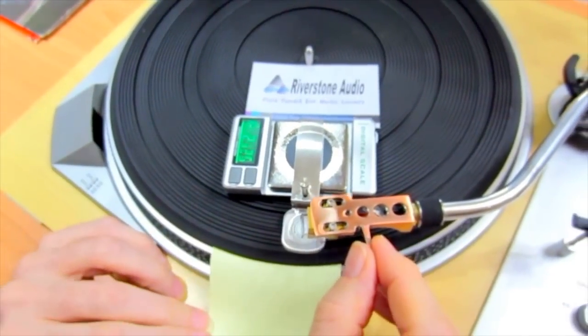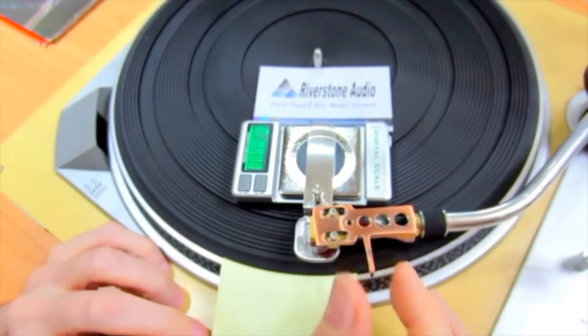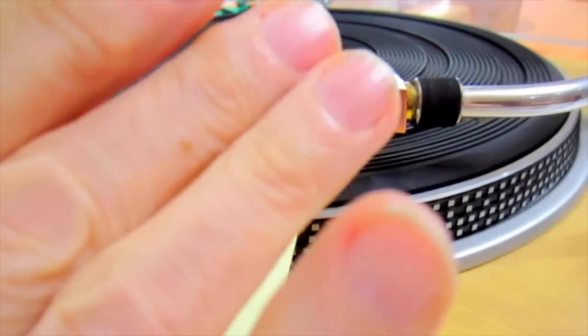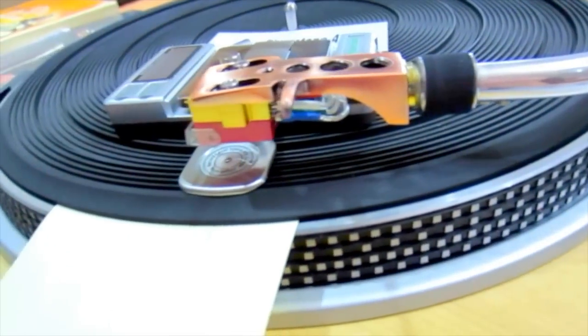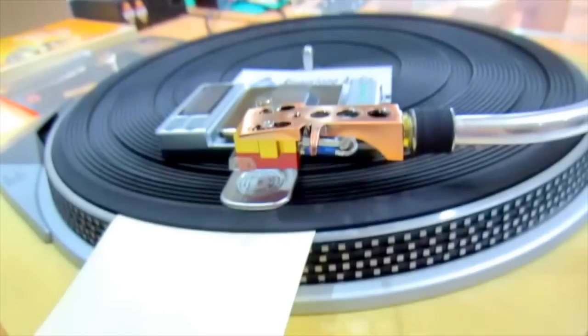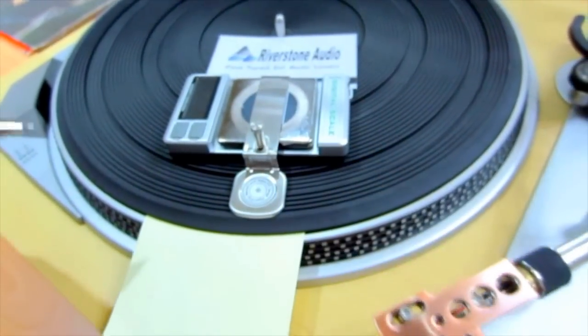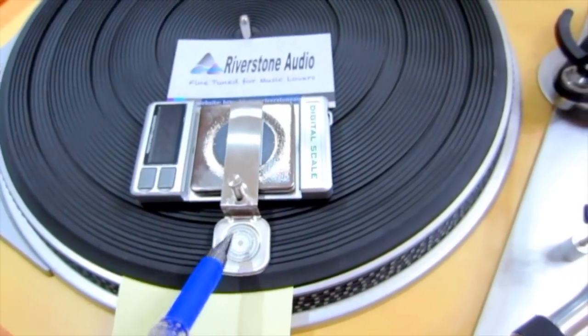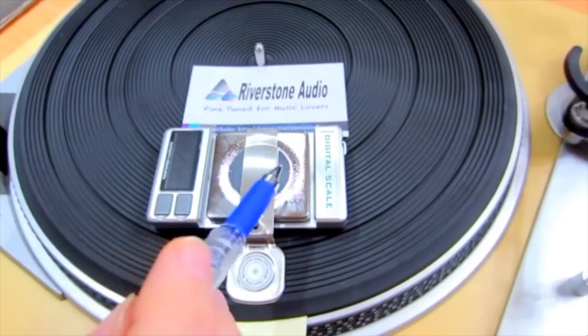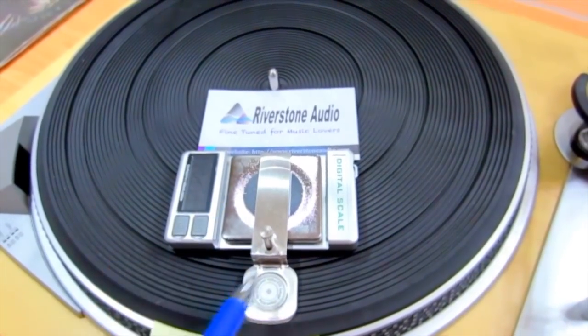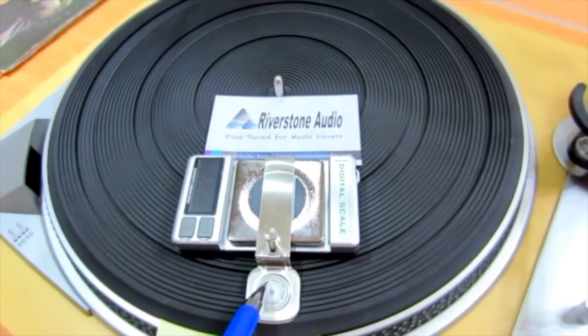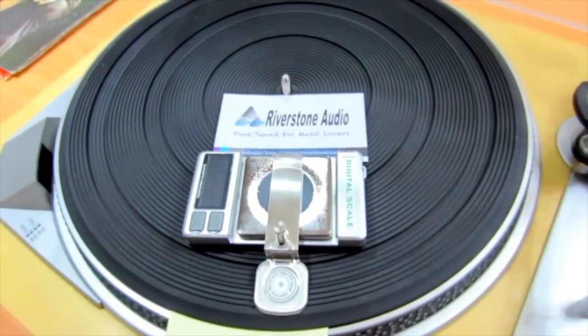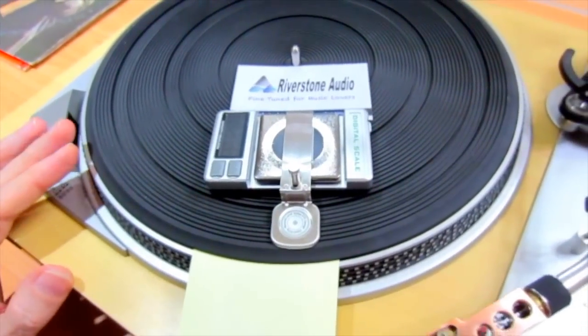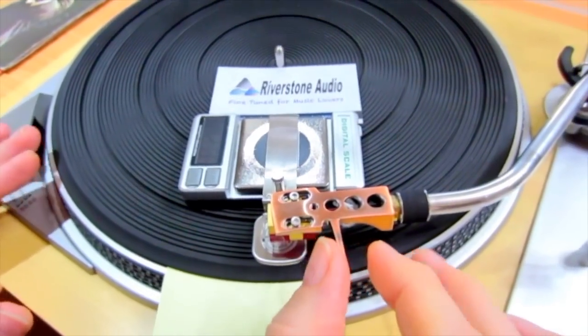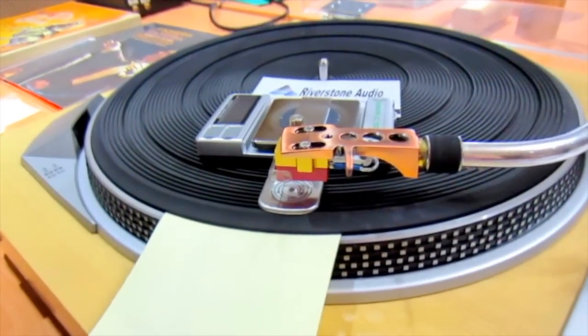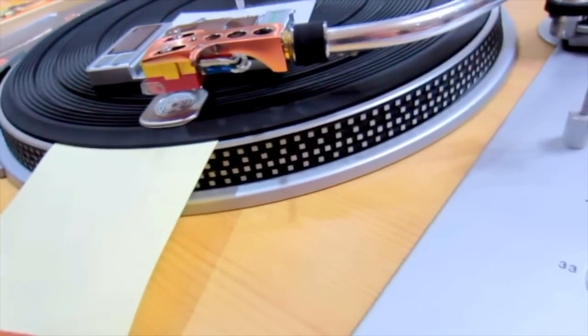All right, now let me go ahead and center. You've got to look at this in two different directions. And again, what I'm doing is trying to center this within the bullseye. Let me pull this arm back away for a moment, just to make one comment. The closer you get to the bullseye, the better, but because I've got a relatively stiff beam here that this cantilever arm is attached to, the strain sensor, anywhere within this inner circle is fine. You won't get any difference in reading on this polymer pad. But probably the closer to the center, if it makes you feel better, do it that way. So in two different directions, it looks like I'll be centered.